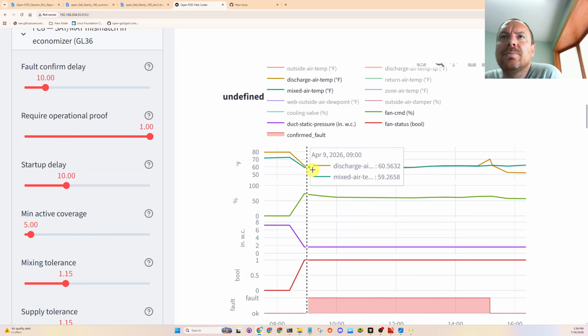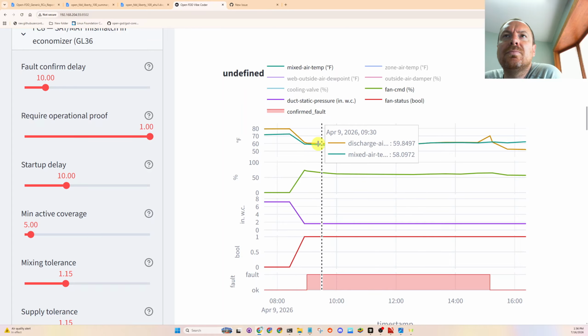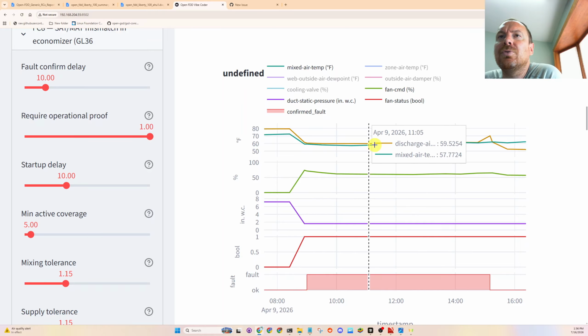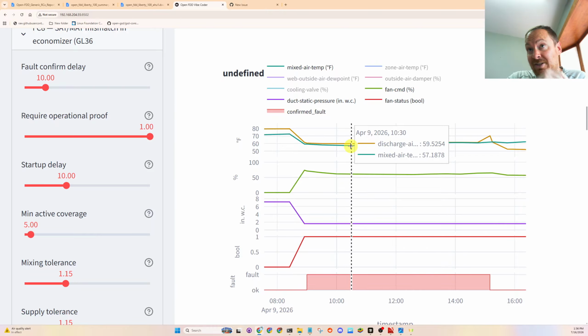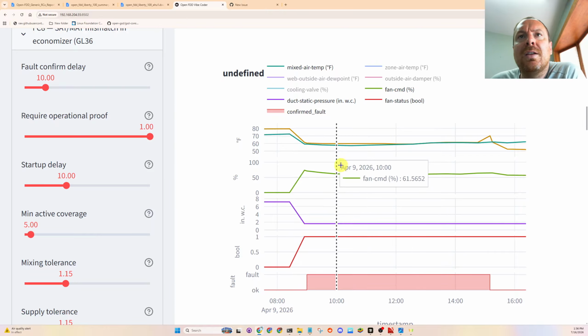Those look pretty close to me. So this is just something that needs to be tuned. Discharge air temp, and that's perfect. A 2-degree rise across the fan, just like what Guideline 36 would recommend. And we do, oh, this is fan.